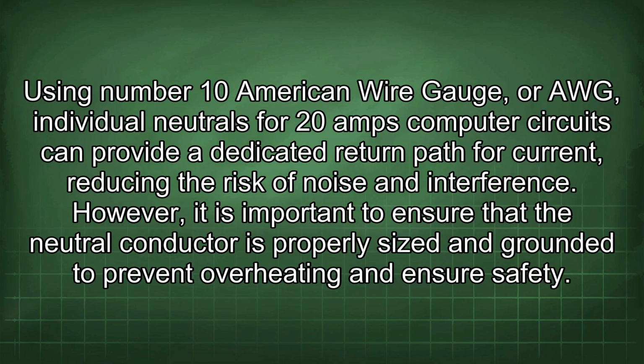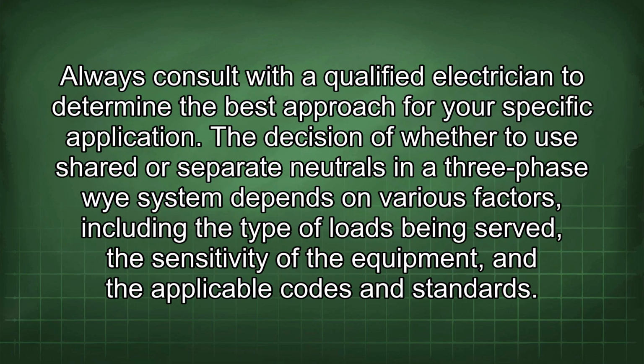Using number 10 American wire gauge, or AWG, individual neutrals for 20 amp computer circuits can provide a dedicated return path for current, reducing the risk of noise and interference. However, it is important to ensure that the neutral conductor is properly sized and grounded to prevent overheating and ensure safety. Always consult with a qualified electrician to determine the best approach for your specific application.